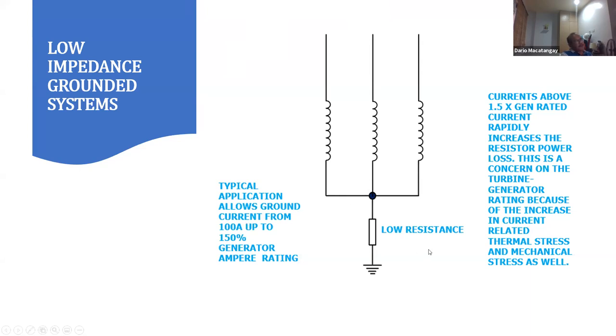Now, the problem with this is that after you reach the 150%, it's sometimes complex or difficult to prevent damage to the turbine generator because of the high I squared R, current squared times resistance. It's energy. This additional energy needs to be dissipated.